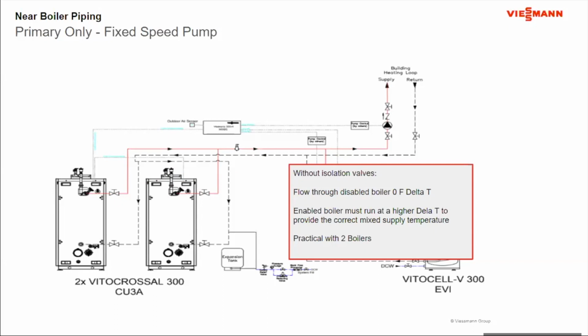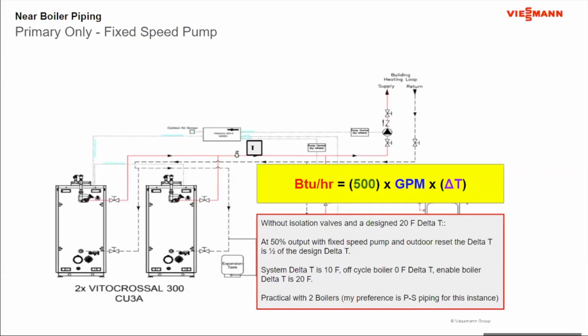Now, that's a theoretical number at maximum fire. Luckily, these typically run off of outdoor reset, and outdoor reset works in our favor to get the delta T down. Okay, so back to the BTU formula. If the system was designed for a 20-degree delta T, and the building is running off of outdoor reset, when the outside temperature is such that the delta T from inside to outside is half the design temperature.